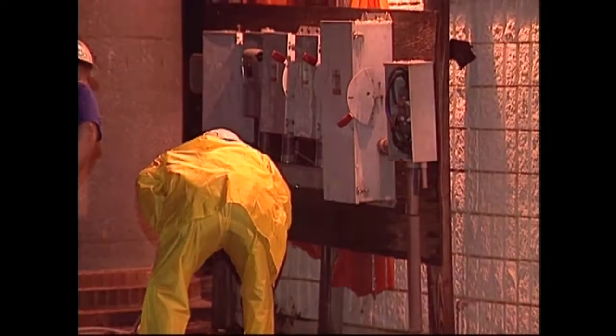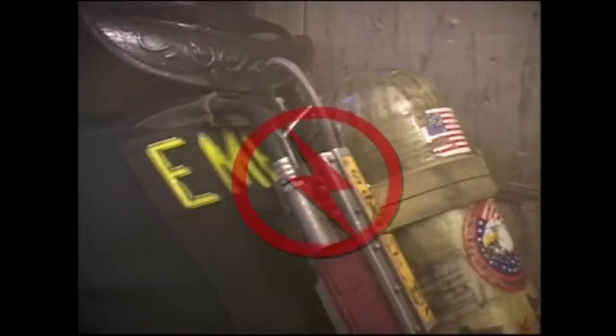Once power has been shut off, with full protective equipment and breathable air supplied and monitored, the chamber can be entered. All the rules for confined space entry must be followed, and extra caution has to be taken to avoid sparking, such as from flashlights being turned on or metal scraped, because of the possible presence of combustible gases.